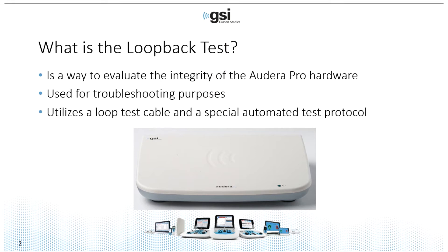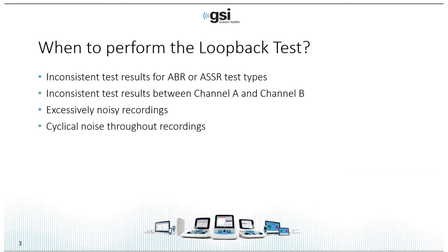The loopback test is used for troubleshooting purposes, only when you suspect there may be a problem with your equipment. You're going to perform the loopback test anytime you're getting inconsistent test results for ABR or ASSR test types. Maybe the results are inconsistent between channels — good data in channel A but issues in channel B — or excessively noisy or cyclical noise throughout the recordings.